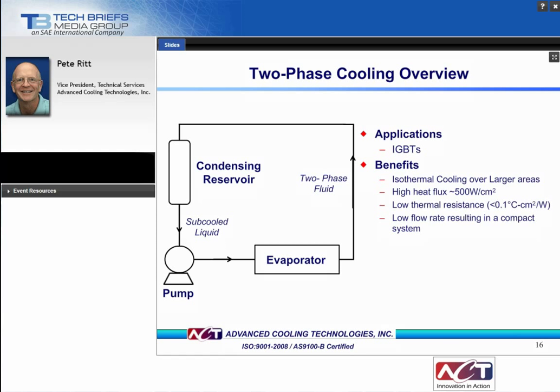Two-phase pump loops have several advantages over liquid-cooled loops. The high latent heat of vaporization allows more heat to be absorbed by the fluid, requiring lower flow rates and smaller pumps. The lower flow rates also typically yield smaller overall pressure drops. Two-phase cold plates are more thermally uniform since heat is transferred to a fluid at a relatively constant saturation temperature with only the vapor quality changing. This compares favorably to single-phase flows, which increase in temperature along the flow paths due to sensible heating of the fluid. Finally, lower evaporator thermal resistances are achieved as higher heat transfer coefficients are associated with two-phase flow.